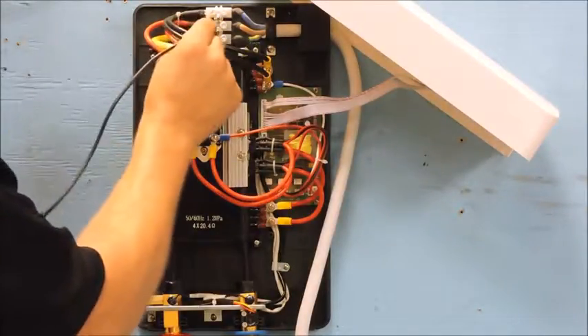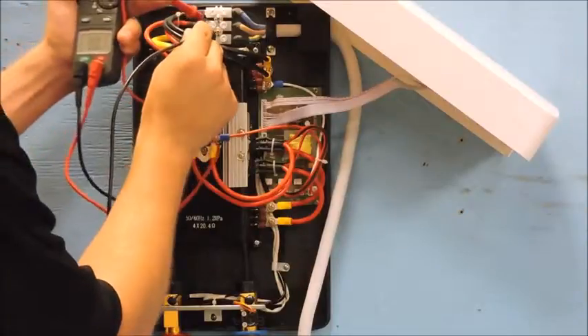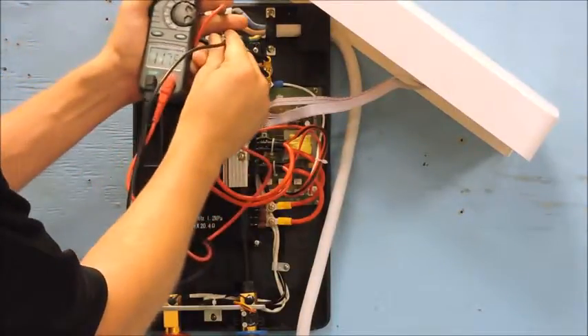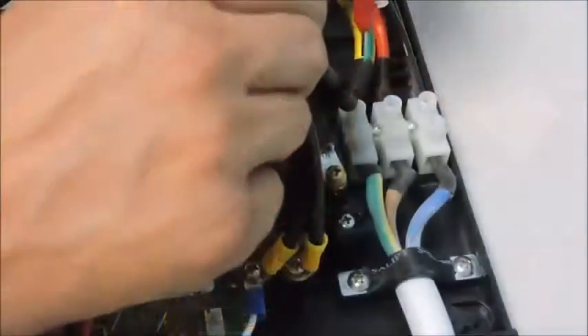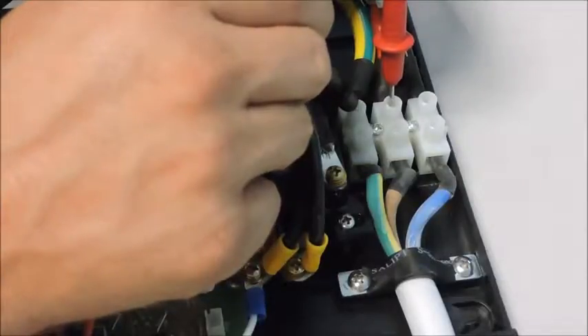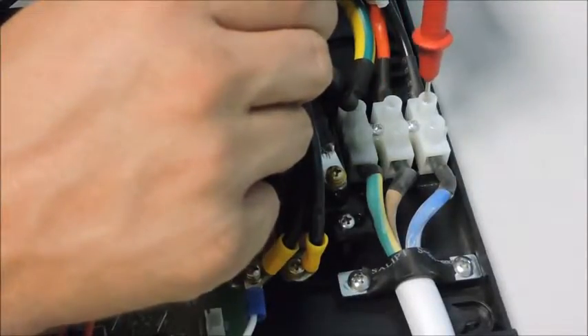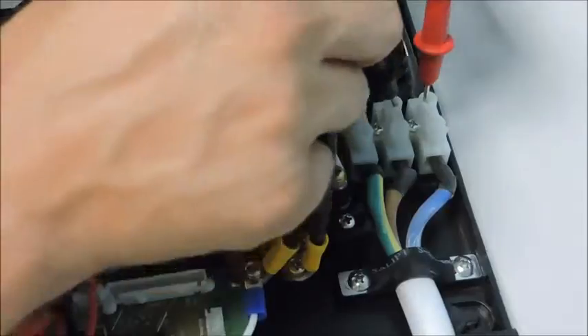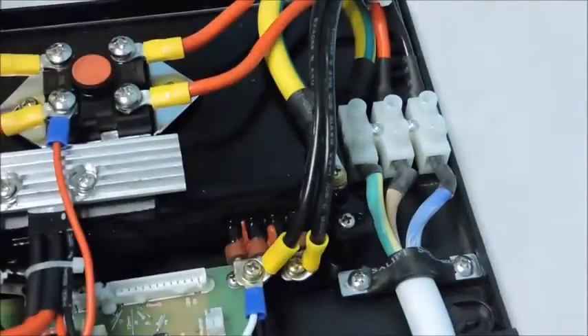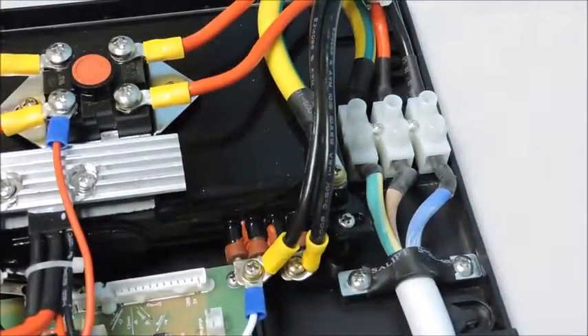Put the black probe on the ground and the red probe on L1, then L2 of the terminal block. Both should read roughly 110 to 120 volts. Then confirm 220 volts by placing the black probe on L1 and the red probe on L2.